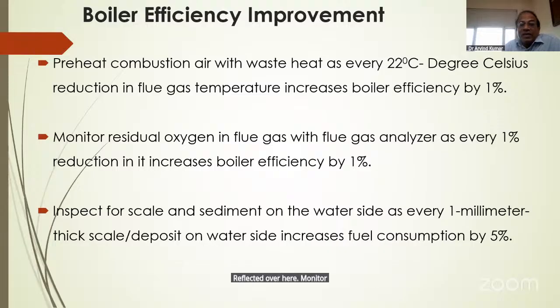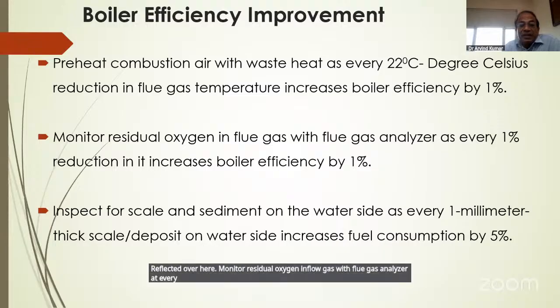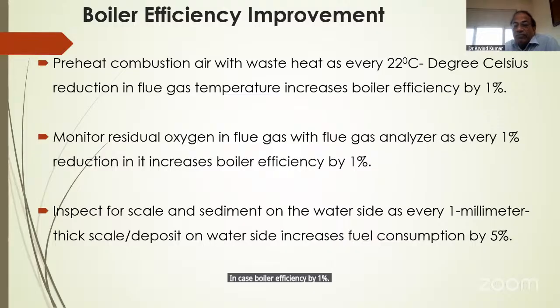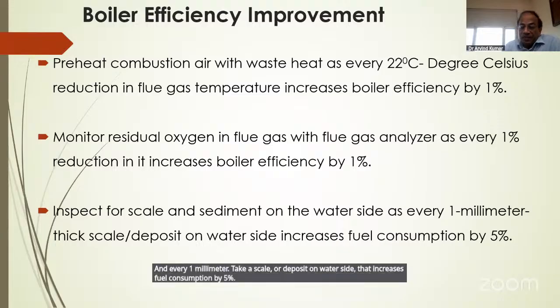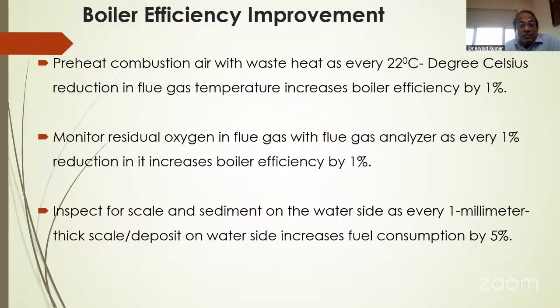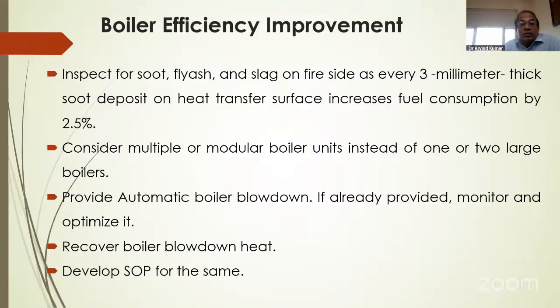Monitor residual oxygen in flue gas with a flue gas analyzer. For every 1% reduction in it, boiler efficiency increases by 1%. Inspect for scale and sediments on the water side, as every 1 millimeter thick scale or deposit on the water side increases fuel consumption by 5%. Inspect for soot, fly ash, and slag on the fire side, as every 3 millimeter thick soot deposit on the heat transfer surface increases fuel consumption by 2.5%.